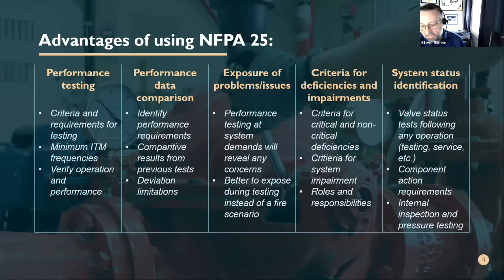Critical and non-critical deficiencies, that is very much subjective for the most part. So you're relying on those trained and qualified doing it to identify. That's your checklist of preventative maintenance that does have to be done or put on there. So there are some non-critical improvements or replacements that are needed. Comparable to that is like changing the filter in your furnace. Critical deficiency, that's on the border, and any kind of avoidance of remedy on critical, that's going to lead you to impairment at some point or another, or affect the operation or performance of that system itself. And the last column I have on there is that system status identification.